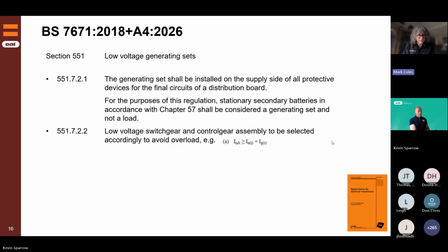The next one is 551.7.2.2, and these are indents describing how, where a generating set is added to an installation, you've got to be careful - because let's say your busbars are rated at 100 amps.